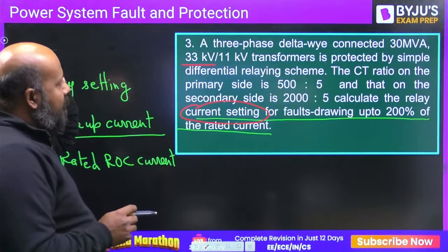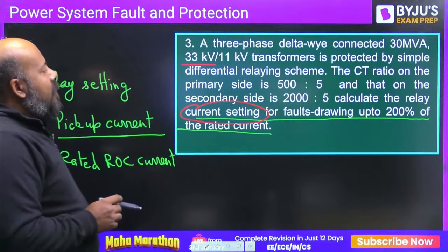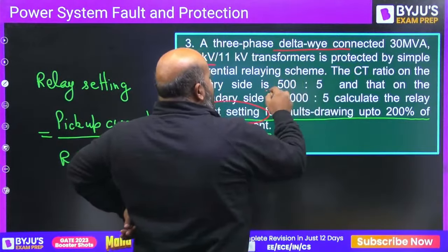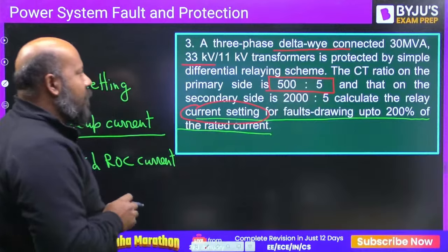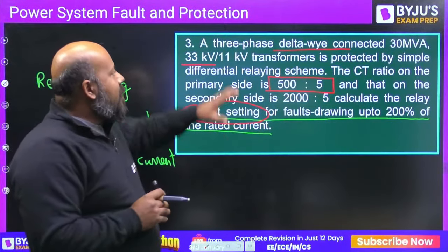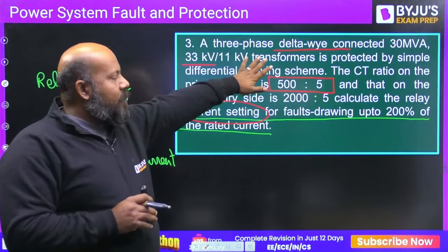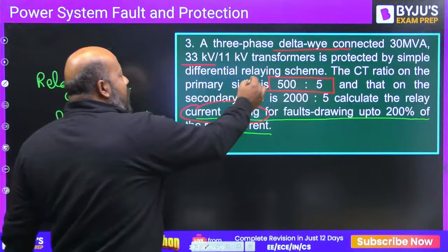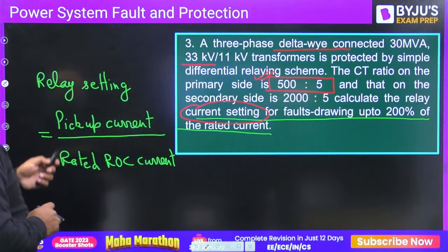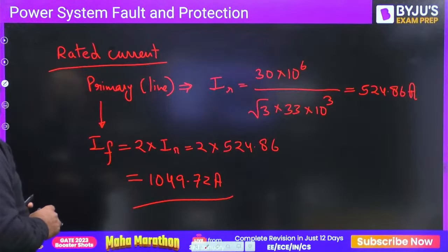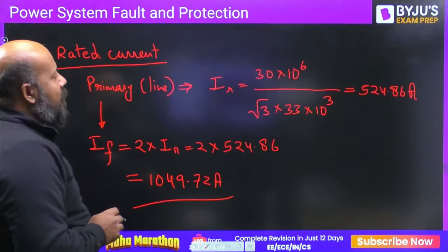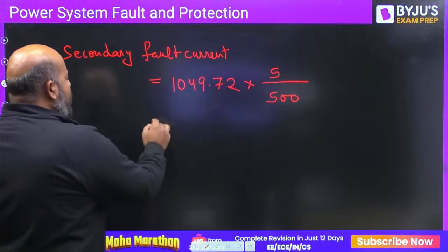CT ratio on the primary side. Okay, this is for the delta Y transformer. So this is the primary of the transformer. Okay, you understand, actually there are two transformers. This is a transformer itself, and the transformer primary connected with the line, you have to reflect it to the CT secondary. So this is the ratio which we have to use, the CT connected to the primary side, because the transformer primary is going to have the line current. So this is going to be 5 upon 500. We have to divide by a higher value to get a smaller value. So 500 is to 5, we are writing as 5 upon 500.